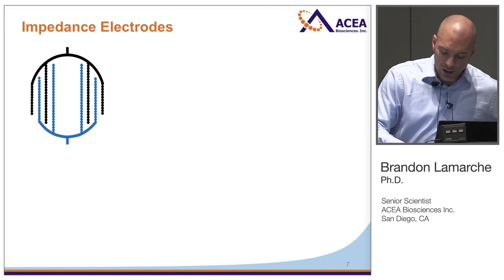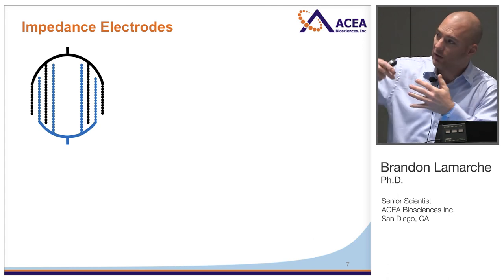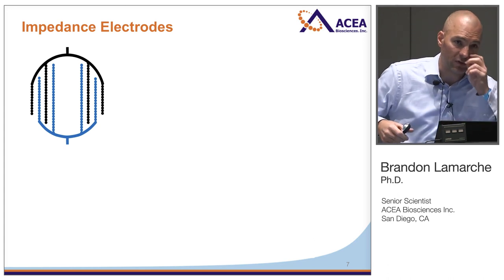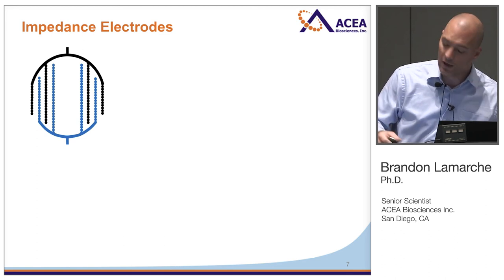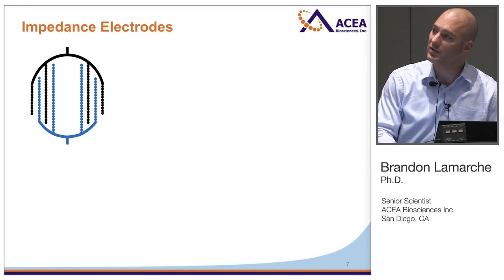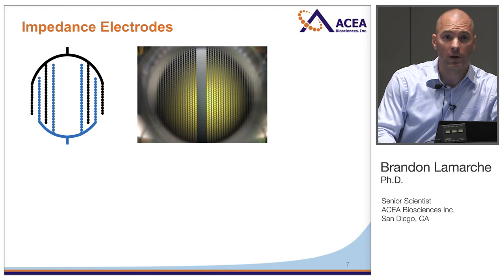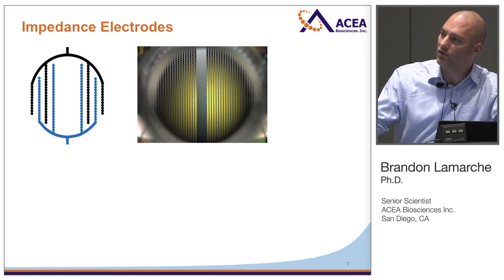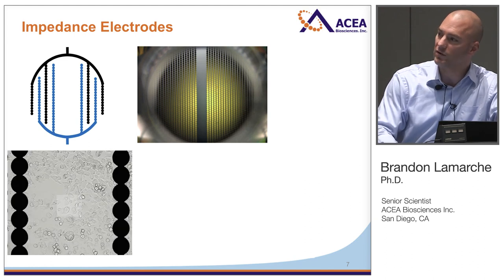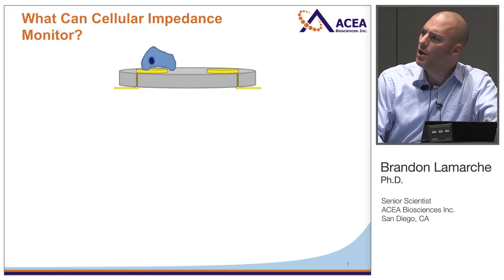What I just showed is actually a simplification — there's actually an array of electrodes that are interdigitated, allowing coverage of about 75% of the plate bottom. This allows monitoring of thousands of cells simultaneously, making it very sensitive. Shown here is a photograph looking down inside one of the 96 wells; you can see a window that allows for microscopy studies, including bright field and immunofluorescence imaging.